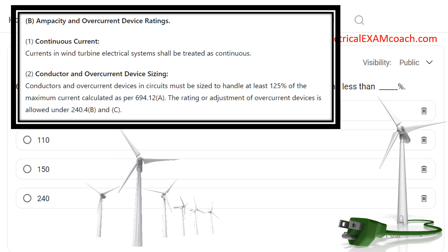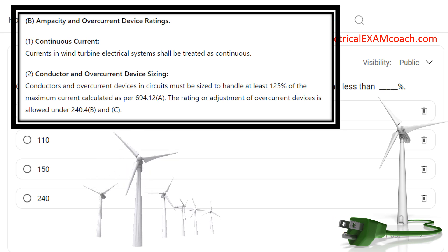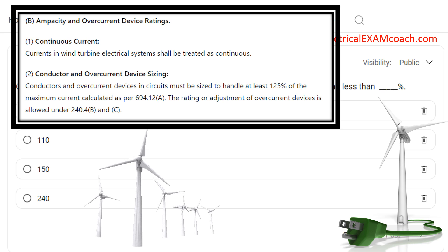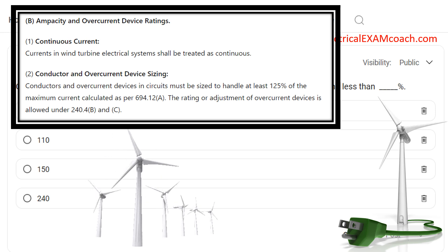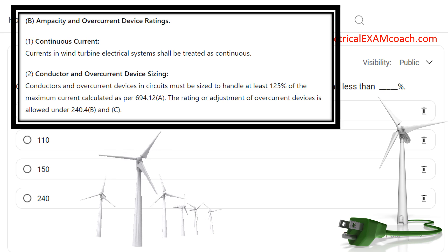Let's say we had a known load of 94 amps, a wire that was rated for 95 amps, and we wanted to protect it with a 100 amp breaker. Just like in other parts of the code, that would be totally fine. We've covered the known load of 94 amps, our wire is good for 95, and we're allowed to protect it with the next standard size up. In this case, we would be code compliant. These same rules apply for wind turbines.